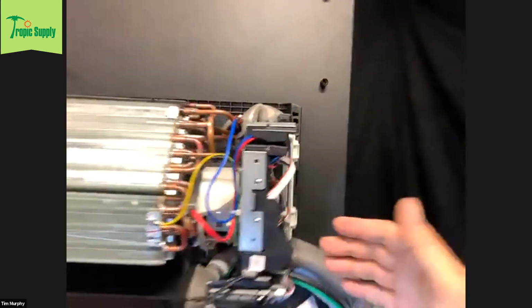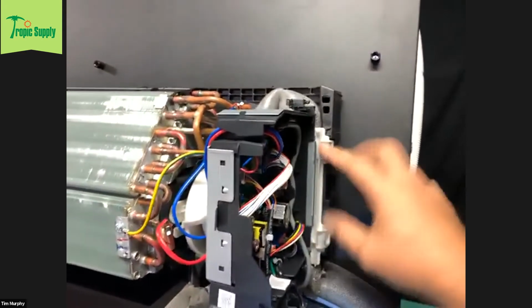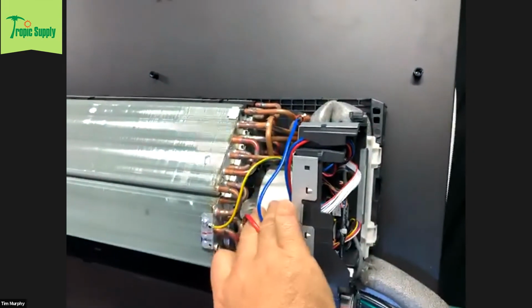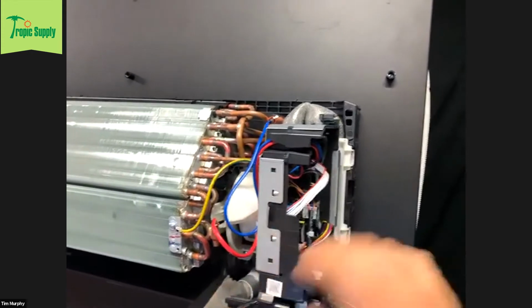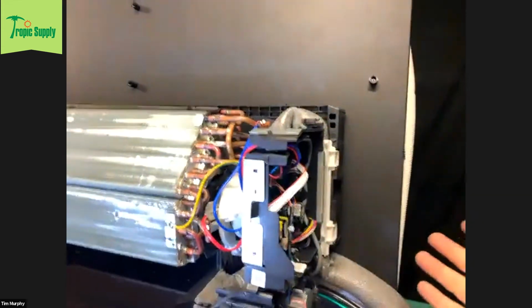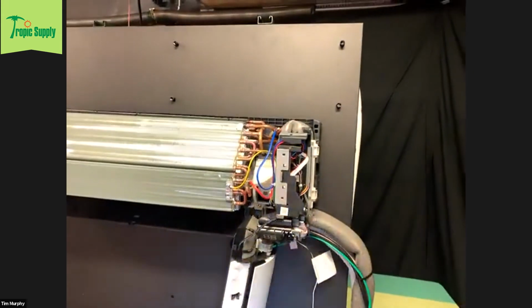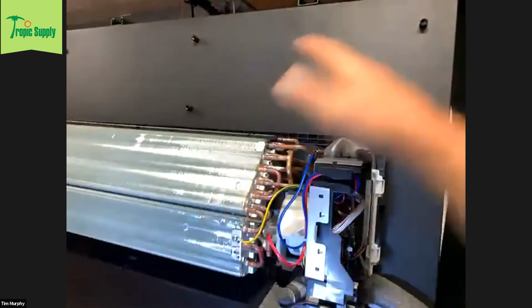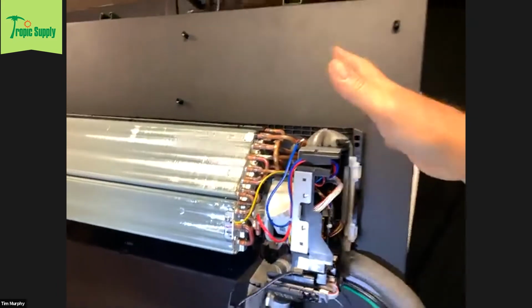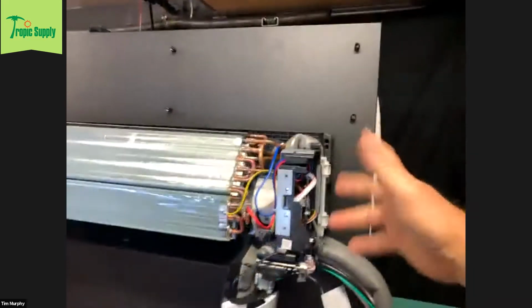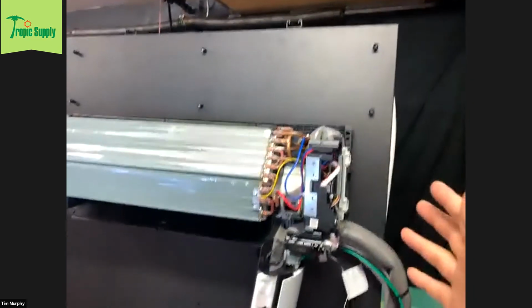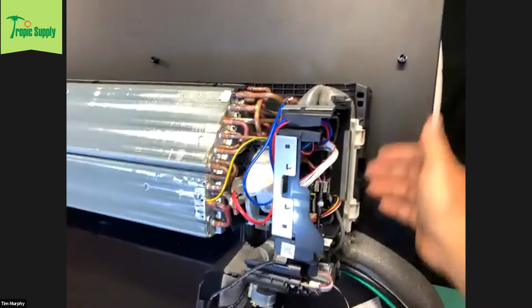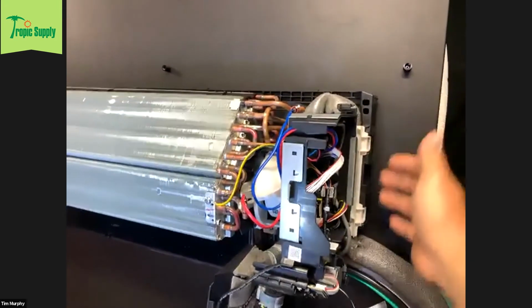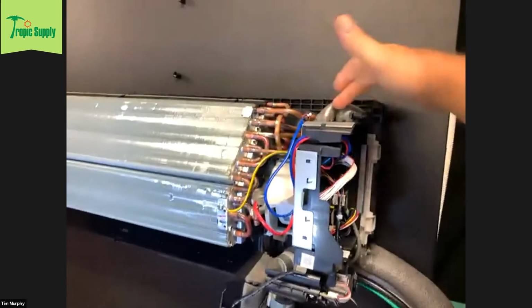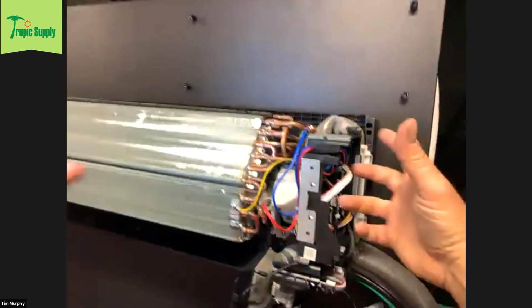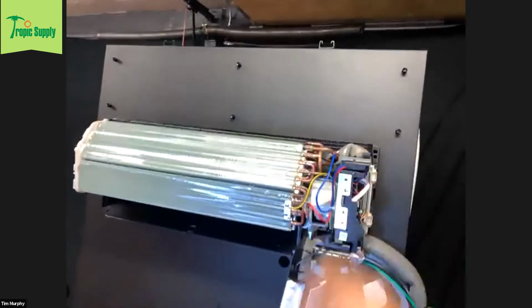You also see this white clip here. Once the blower motor is removed, you can take this clip out if needed. I don't see too many situations where you'd want to remove the coil and leave the back plate on. Typically, if you're removing the coil, it's just easier to take the whole system off the wall. But if you need to, you just take this little white piece, it's not even a screw, it's just a clip, and it clips out. The copper that runs behind it allows you to gain access and pull that coil completely out of the wall bracket.